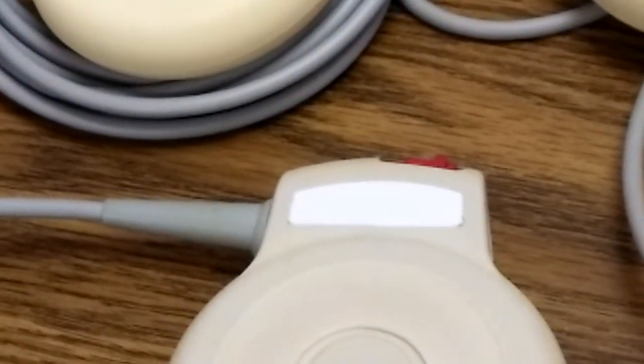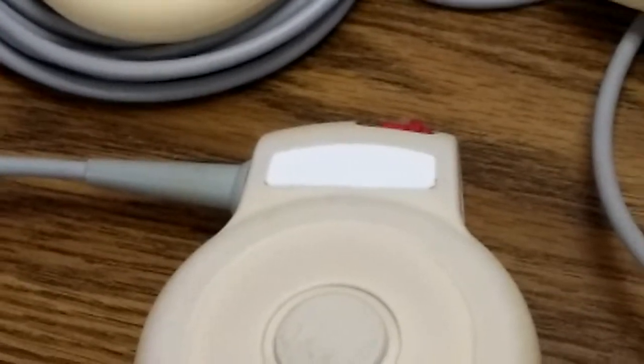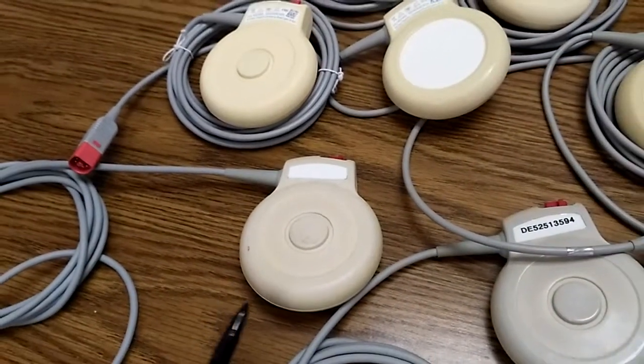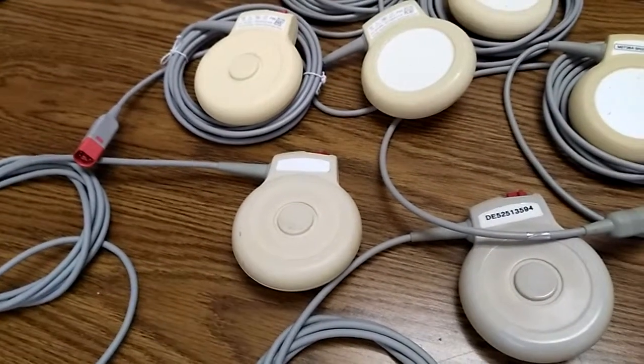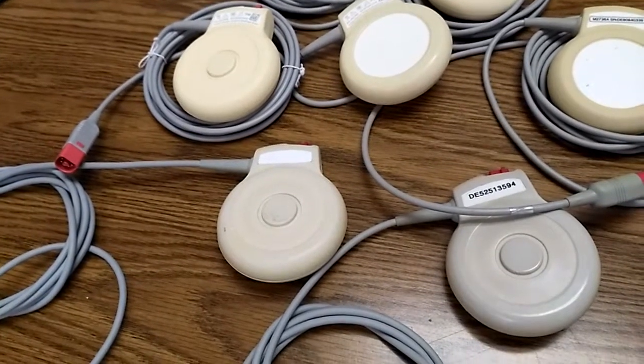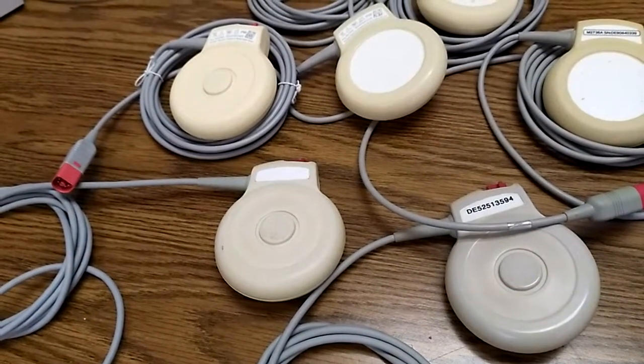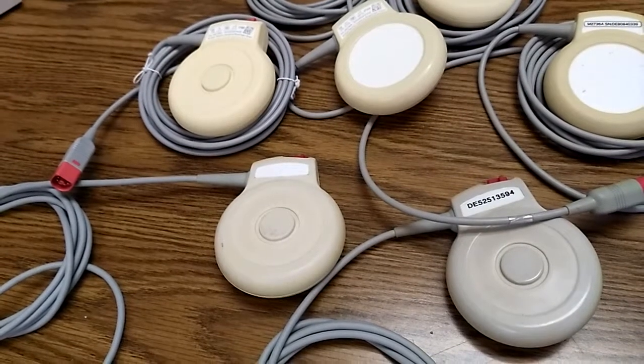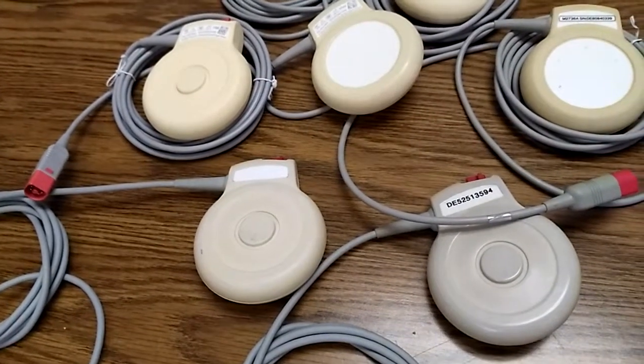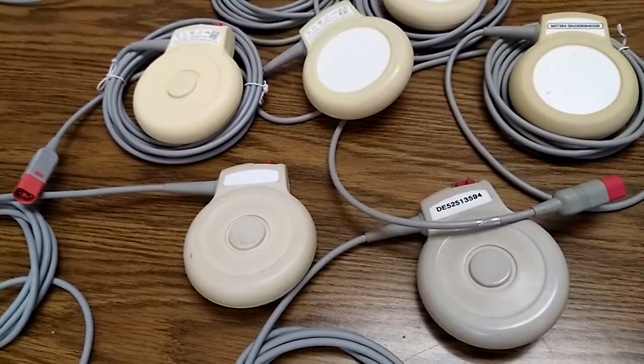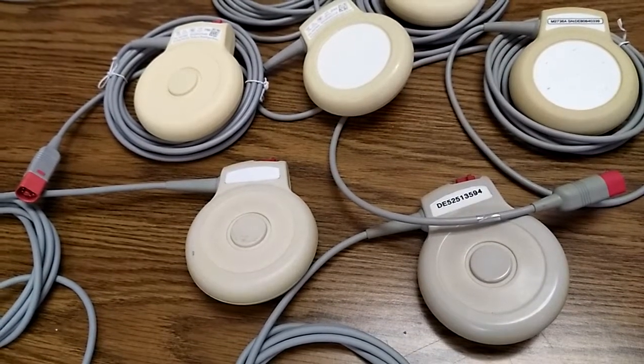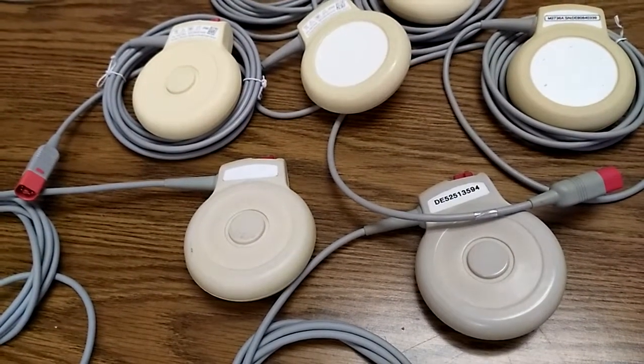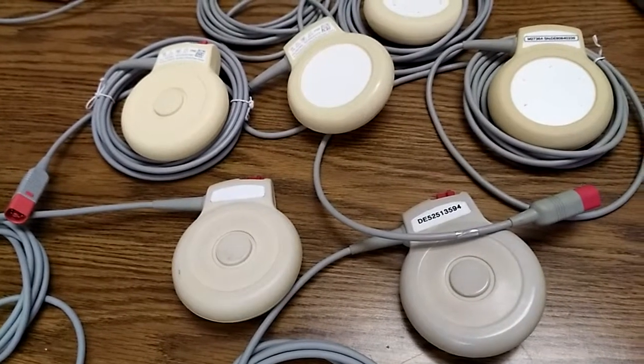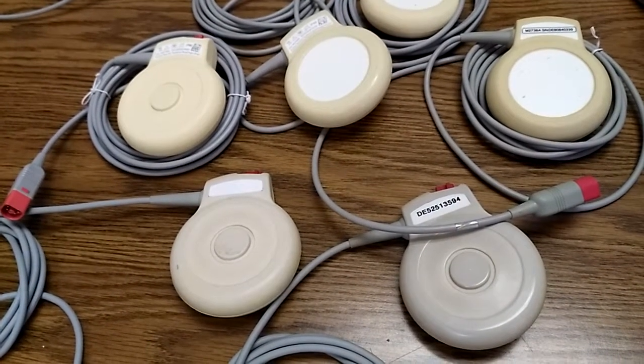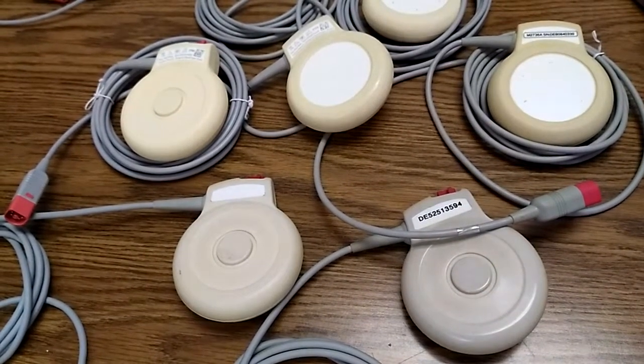The problem with transducers repaired using non-Philips plastic cases and parts, as you see here, is, number one, the Toco baseline drifts. They pick up spurious noise signal even when there is no contraction. Sometimes it could be misinterpreted as if there is a contraction taking place. In some events, even when a very strong contraction is there, the transducer does not pick up anything, as if it has gone into saturation.